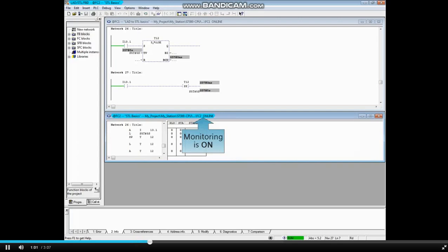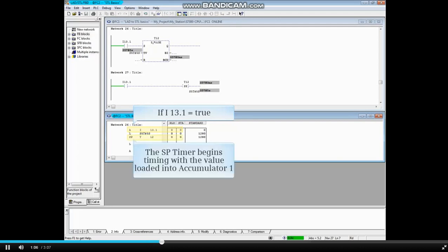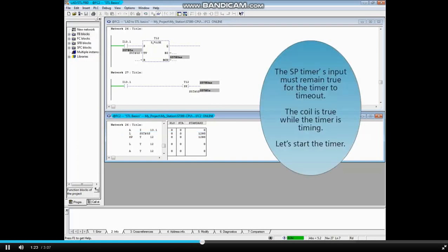Monitoring is on. When I 13.1 is true, the SP or pulse timer number 12 will time according to the value in accumulator 1. The value that has been loaded into accumulator 1 is S5T pound five seconds. The SP timer's input must remain true for the timer to time out. The coil is true while the timer is timing.